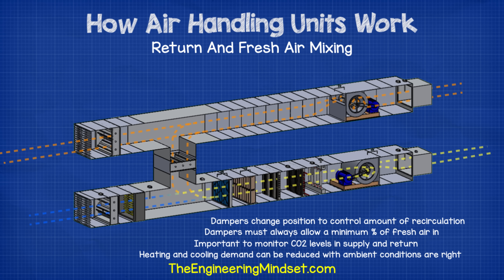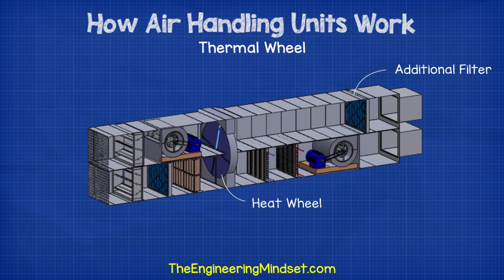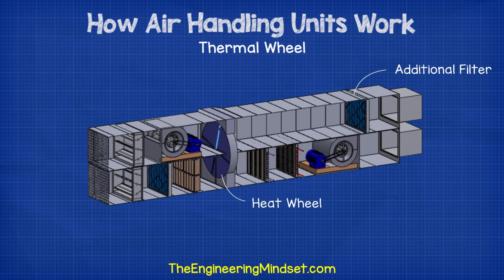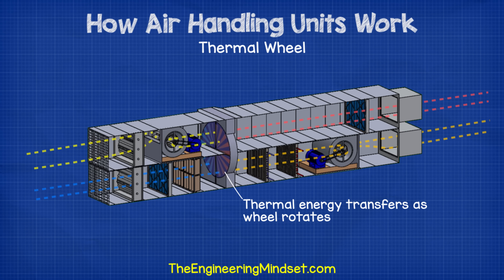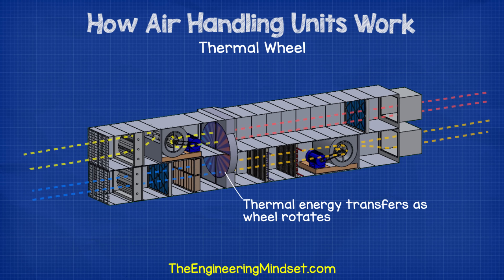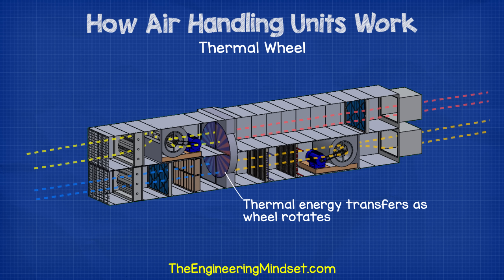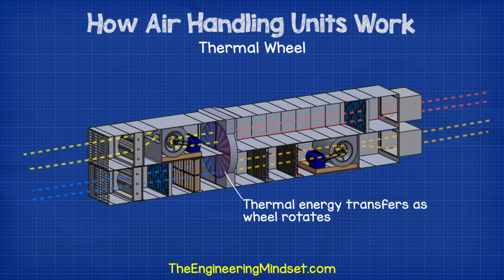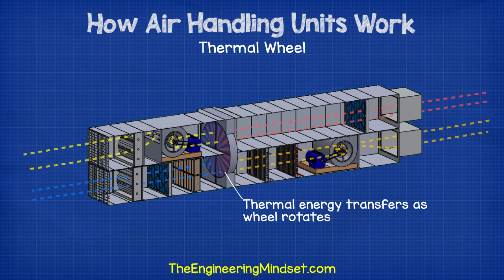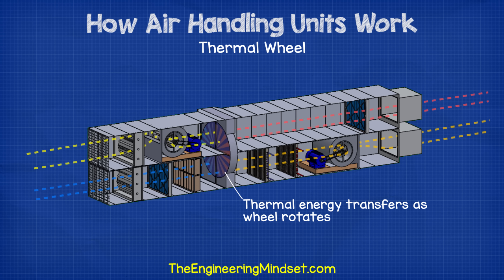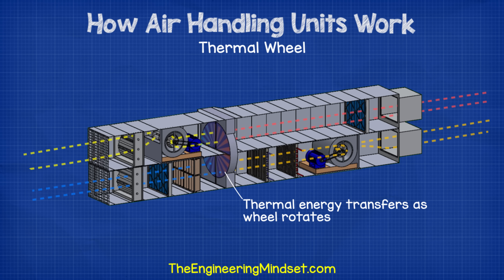Another variation we might come across is the heat wheel — this is very common in newer compact AHUs. This uses a large rotating wheel; half of it sits within the exhaust air stream and half within the fresh air intake. The wheel rotates driven by a small induction motor. As it rotates, it picks up unwanted heat from the exhaust stream and absorbs this into the wheel's material. The wheel then rotates into the fresh air intake stream — this air is at a lower temperature than the exhaust stream, so the heat transfers from the wheel into the fresh air stream, which heats the incoming air and reduces the demand on the heating coil. This is very effective, but some air will leak from the exhaust into the fresh air stream, so this cannot be used in all buildings.